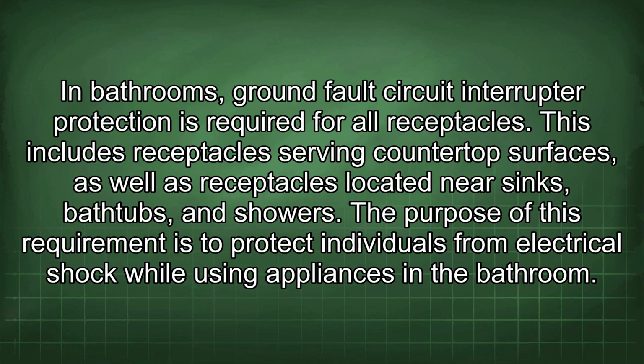In bathrooms, ground fault circuit interrupter protection is required for all receptacles. This includes receptacles serving countertop surfaces, as well as receptacles located near sinks, bathtubs, and showers. The purpose of this requirement is to protect individuals from electrical shock while using appliances in the bathroom.